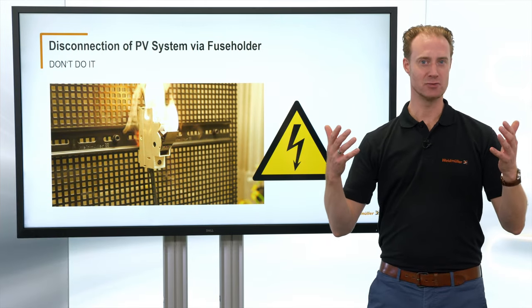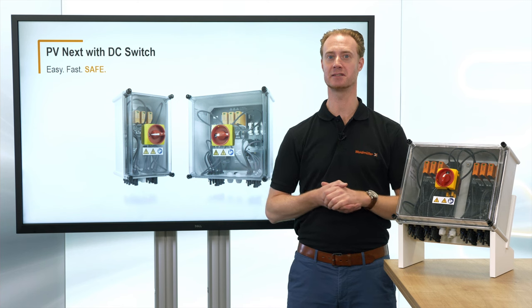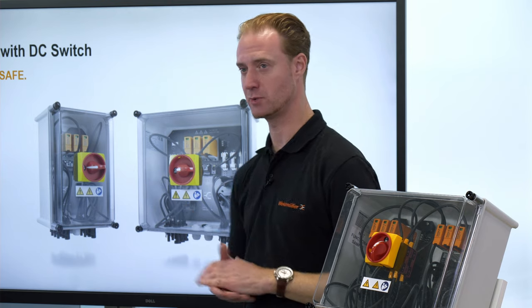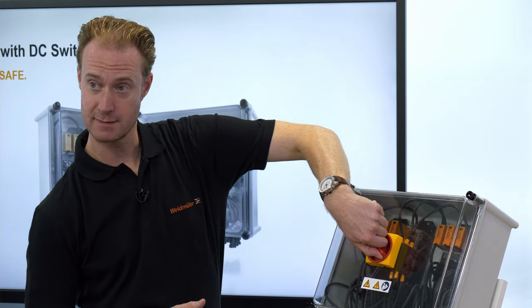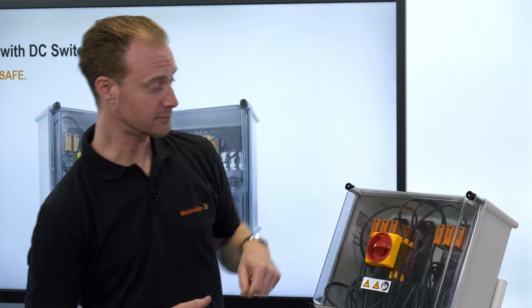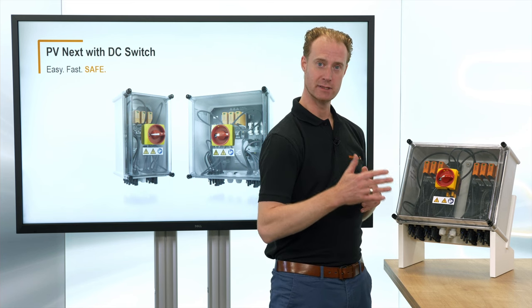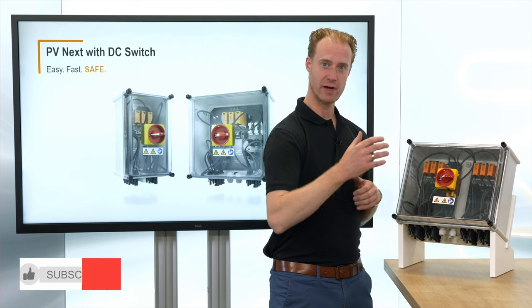Hey Weidmüller, do you have a better solution for me? The safe way to do service and maintenance in a PV installation is to use a PV box with integrated load break switch. The switch has a spring inside which is stressed and then at some point quickly released, and at that moment the strings are disconnected within an instant and the arc which is appearing is cut off very, very quickly.